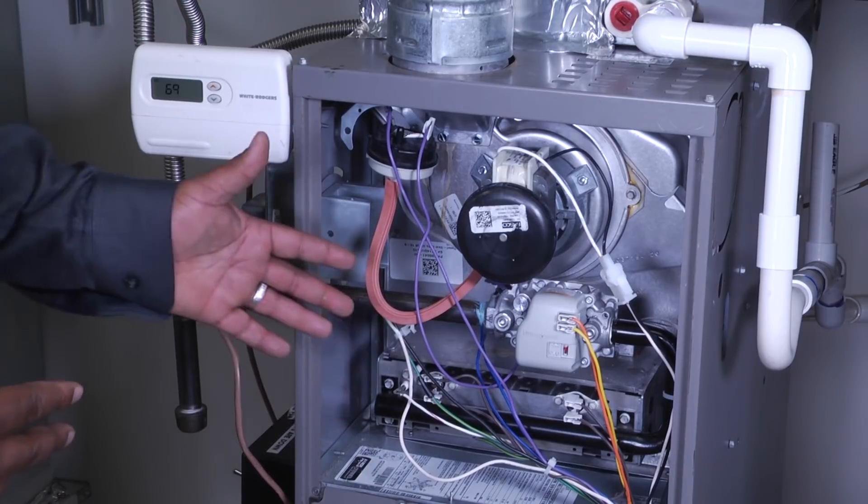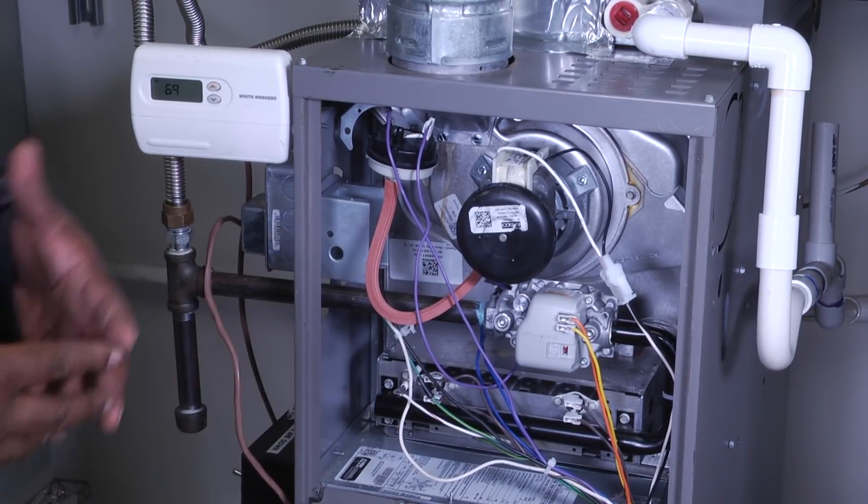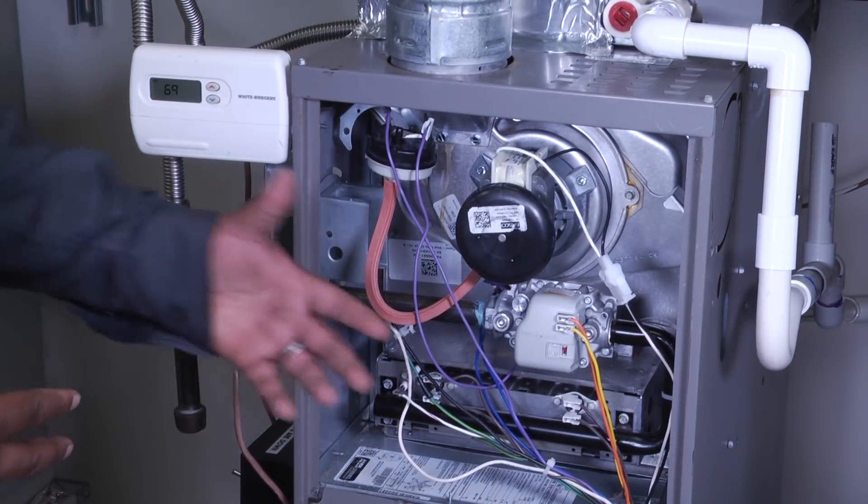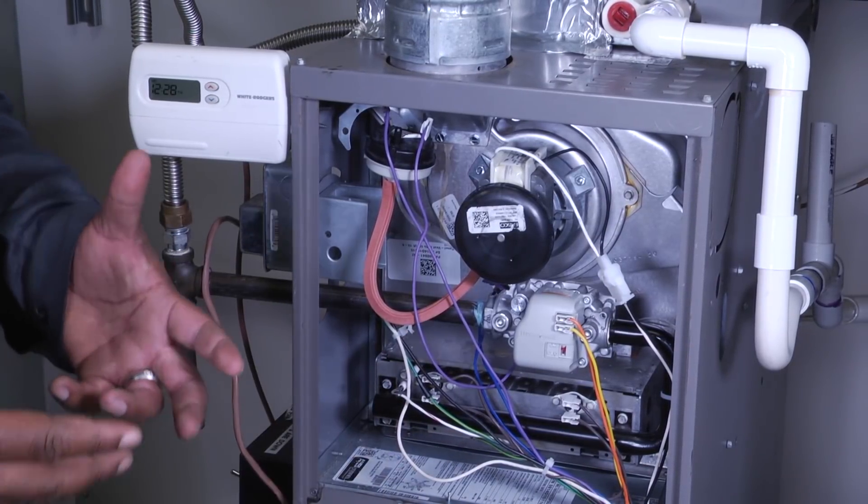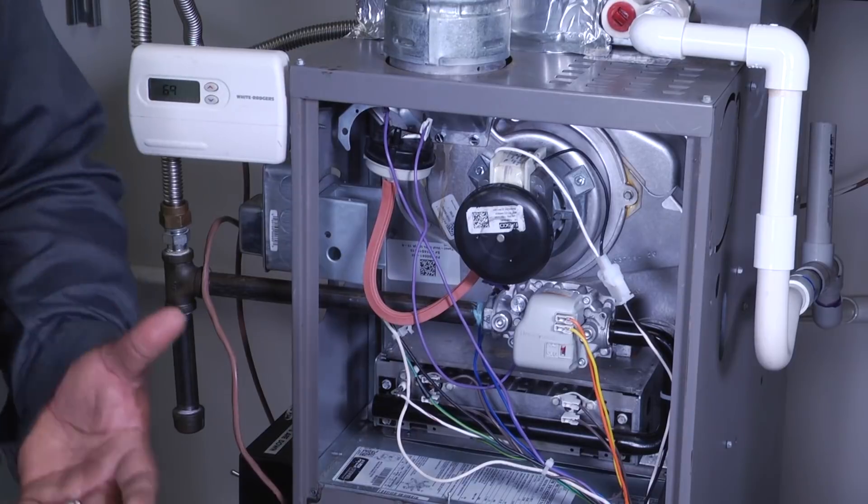On the other end of the hot surface igniter, we have our flame sensor which is going to prove to us that we have a flame, letting the system know that everything is okay. And then finally, our blower motor is going to kick on once we have that heat inside of our heat exchanger and push that heat through the house, thus satisfying our customer.